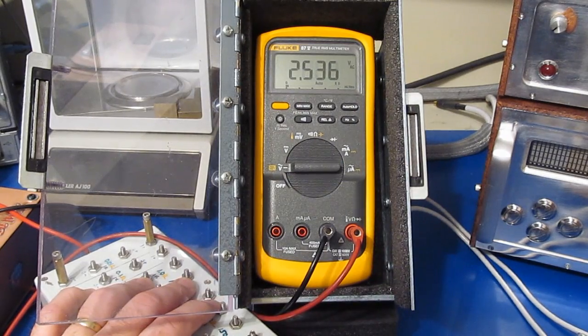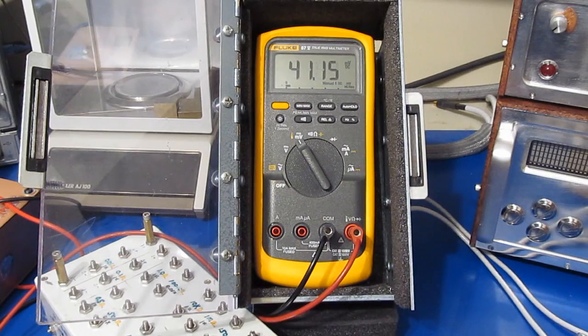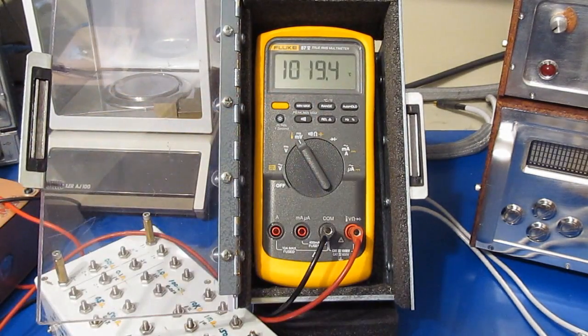That looks fine. Again, 2.5 here, that looks fine. This should be roughly 40 millivolts - that looks fine. This should be a little over 1,000 degrees - that's fine. This should be roughly 500 - looks good. And this should be room temp - that looks fine as well.